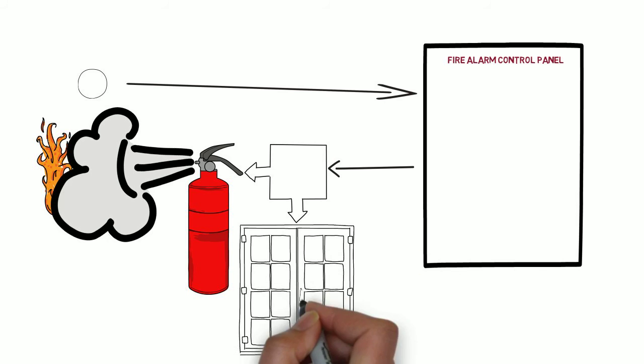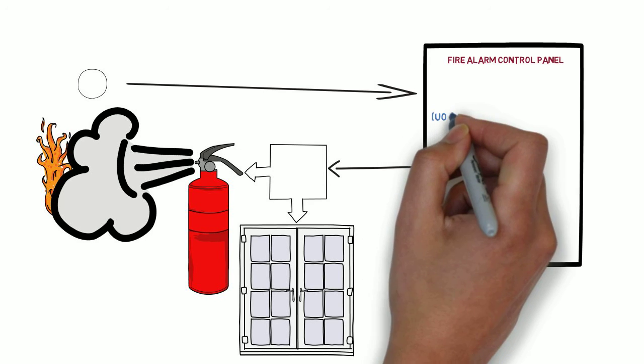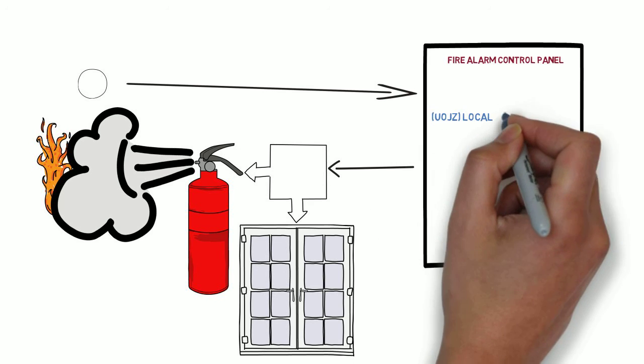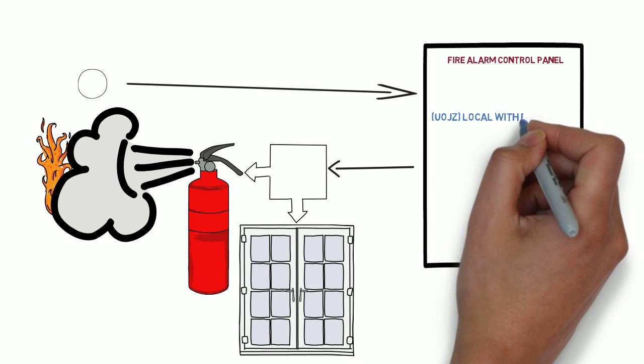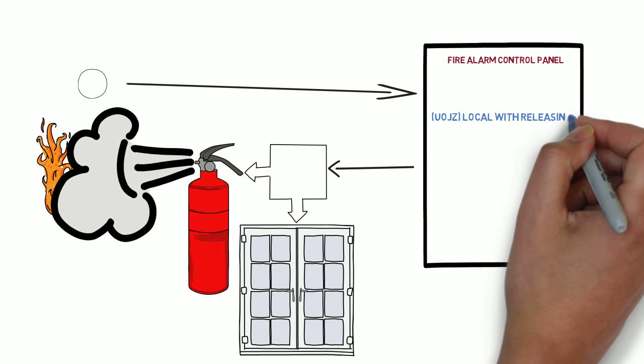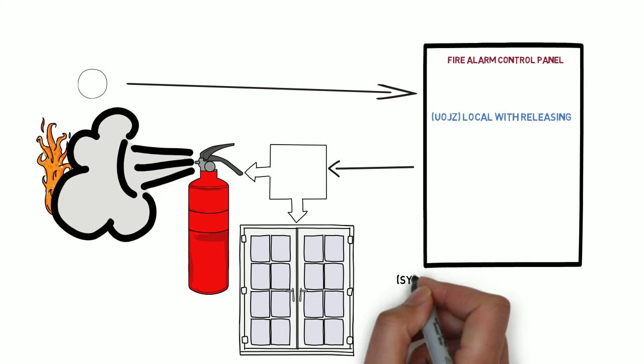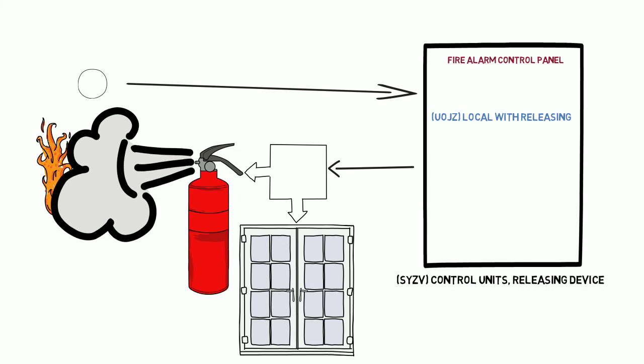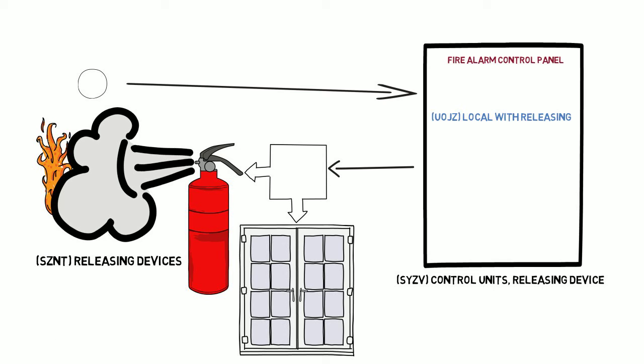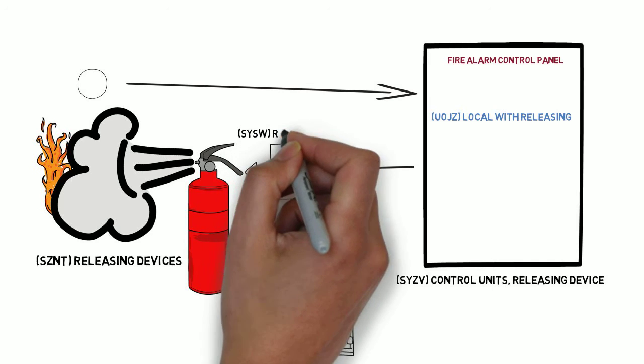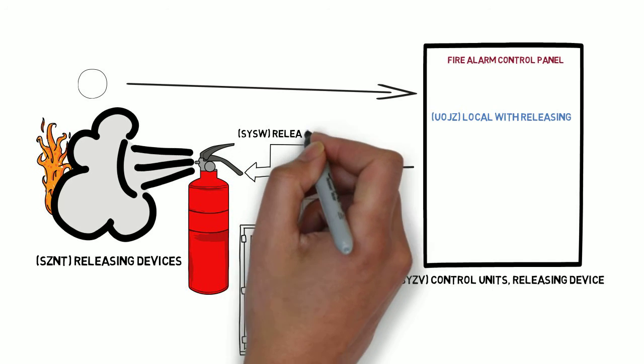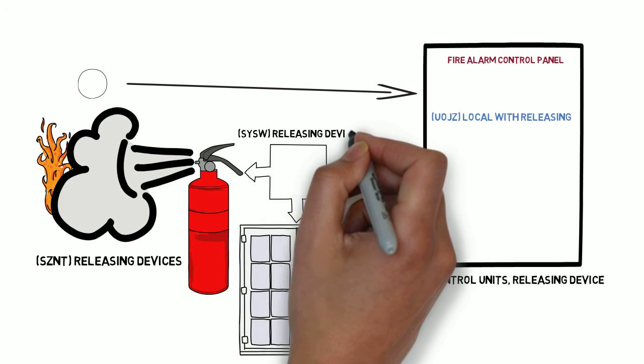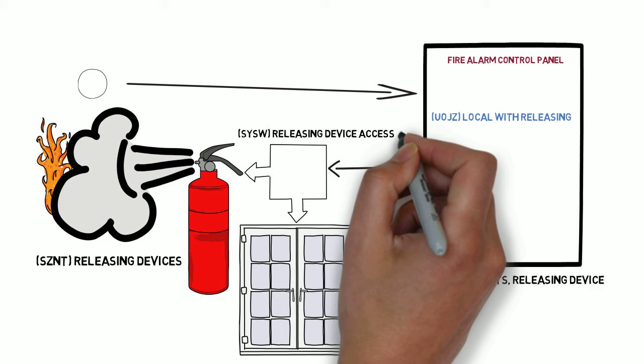A local control unit with releasing is listed under UOJZ as a local and releasing service type. A control unit can have multiple services. A control unit with releasing service but not local service is listed under SYZV control unit's releasing device. Releasing devices and releasing device accessories are listed under SZNT and SYSW respectively.